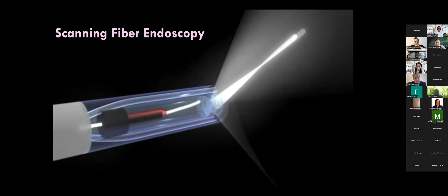Everything that is reflected is captured back by another fiber that goes to a detector and a computer that reconstructs images. All this cycle that you are seeing here, from the center all the way to the periphery, is happening 30 times per second, which means that every single second we are illuminating the field of view 30 times and 30 photos are generated, which is more than enough to create videos. This is another way to see what I was explaining: a mini scanner inside the tip of a 3 French catheter, or 1 millimeter catheter. You can see how the laser goes through tiny lenses, which can adjust for the focal depth and illuminate forward. And what you are seeing here is the spiral path I was explaining before.